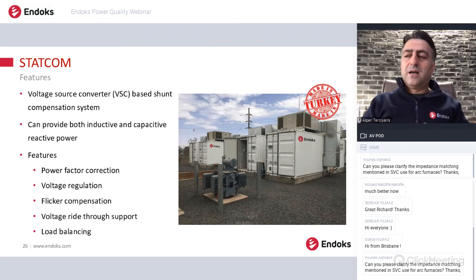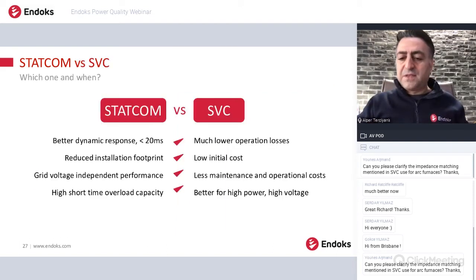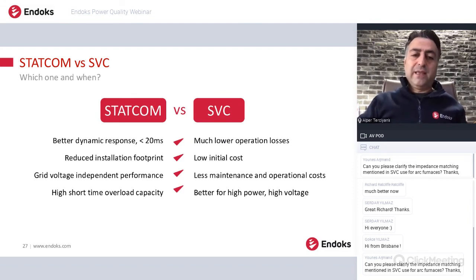Hence, STATCOMs can be used for flicker reduction in power systems, especially if you need a higher flicker reduction ratio. On SVCs, the flicker reduction ratio is around 1.7, but with STATCOM you can have up to 2.1, 2.2 flicker reduction ratio. So if there is a big flicker problem, you can use STATCOM in order to eliminate these flicker problems, because it can act very fast. But of course, there are some disadvantages of STATCOMs as well. These are the benefits, the advantages and disadvantages, and which one to use and when.